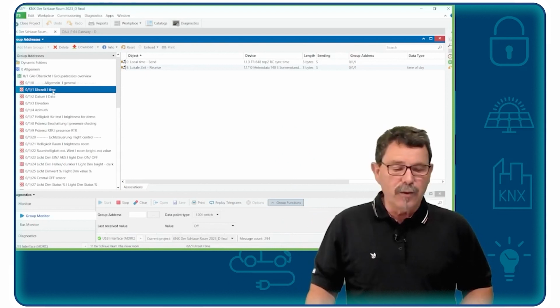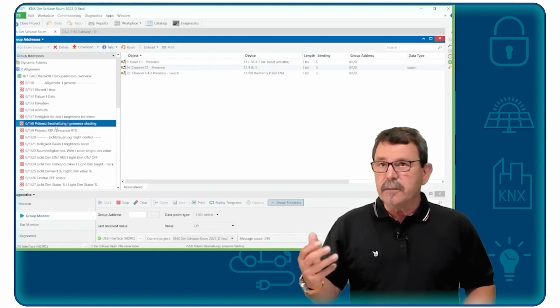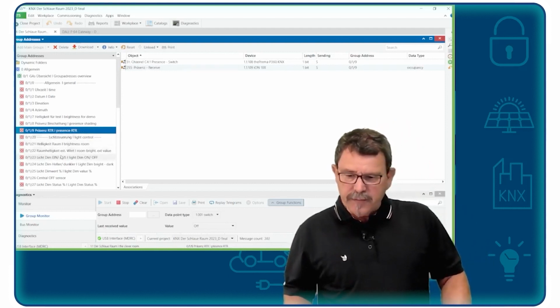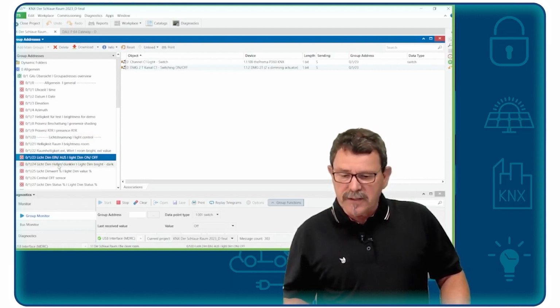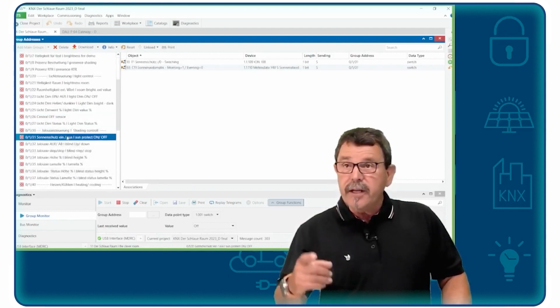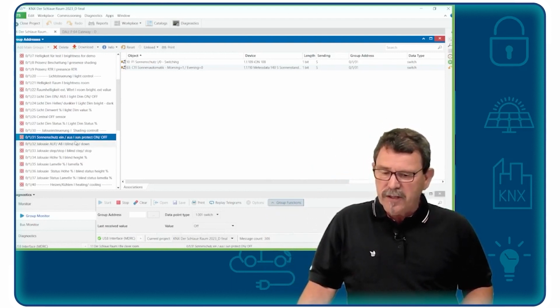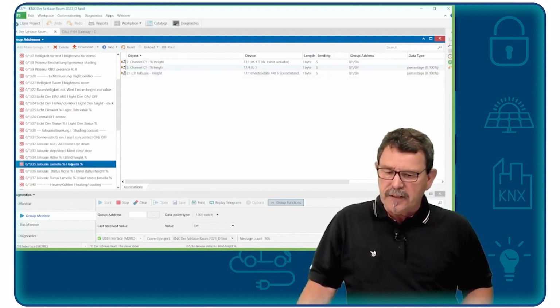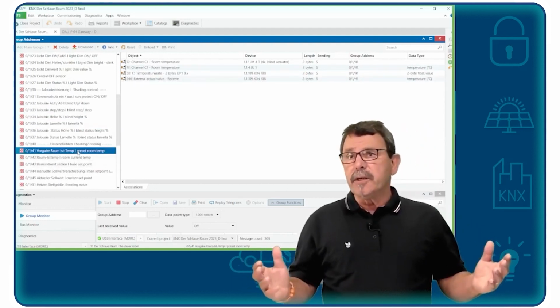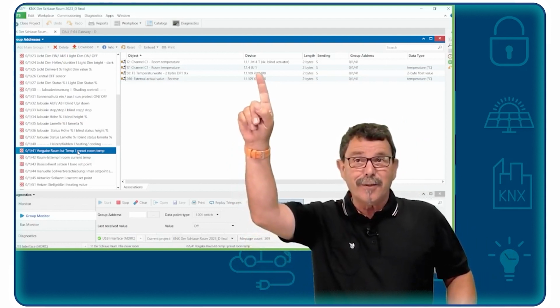You see here the local current time, you need the date, you need finally the presence for the reasonable shading, you need presence for the RTR, for the room temperature control, right? Then we need the light control for the constant light control, then the dimming value and the status or the feedback. We need to control I/O to switch on and off the sun shading, the sun protection finally. We need blinds up, blinds down, height and lamella in this case. And for the HVAC control, we need reasonable room temperature, and that's the thing which we have to consider.